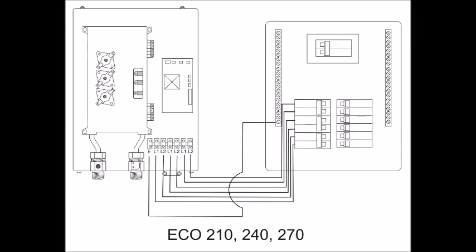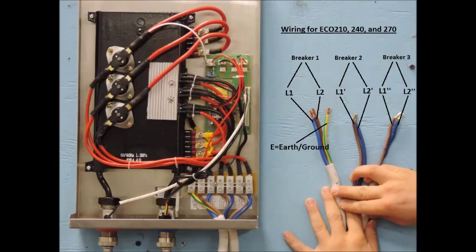With both the line drawings and the real world photo, you will notice that there are two more wires on these units, as compared to our eco-180 unit. These two wires, like the previous wires, should be connected to their own 220V double pole 40A breaker.